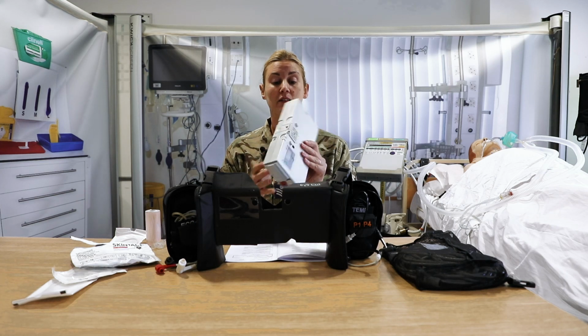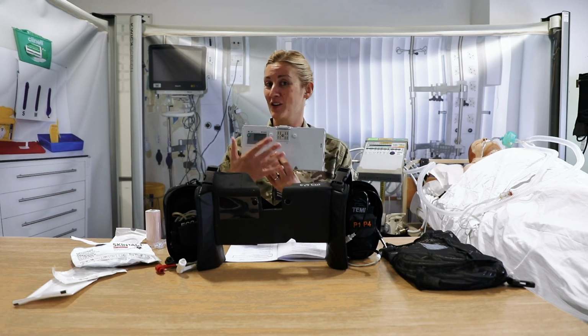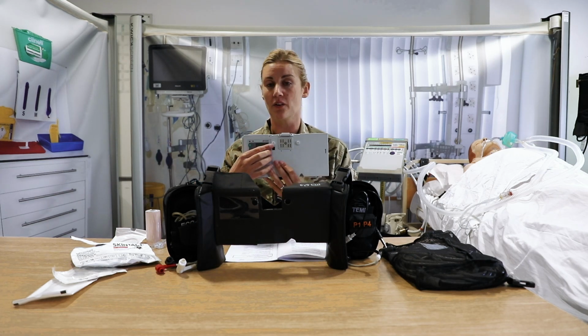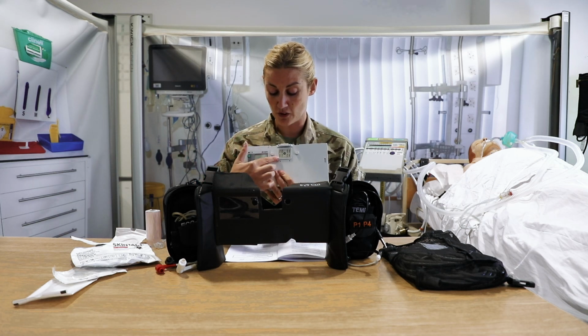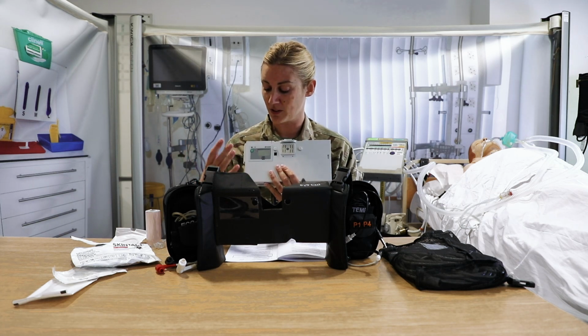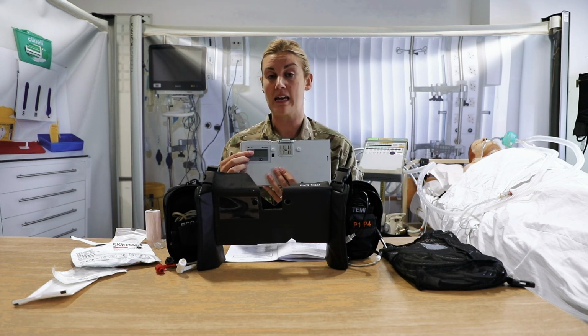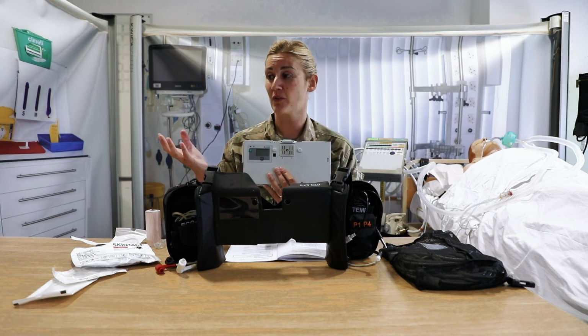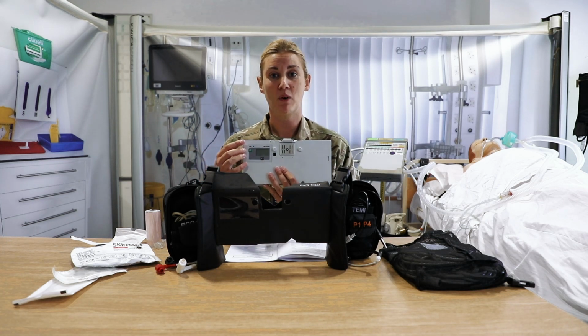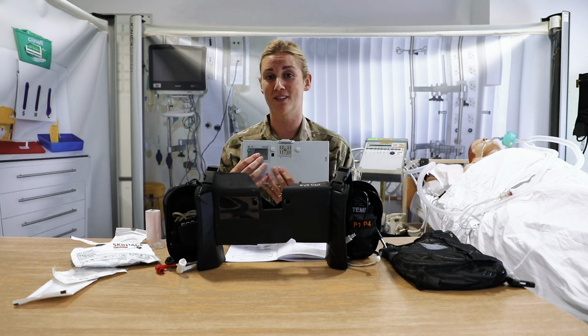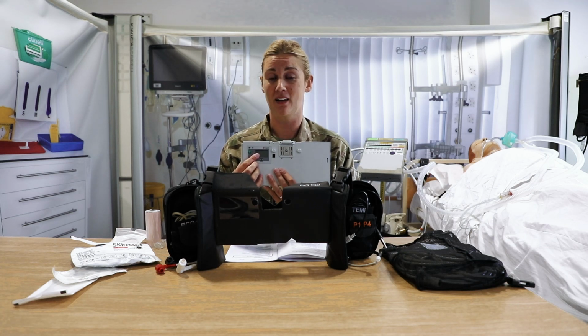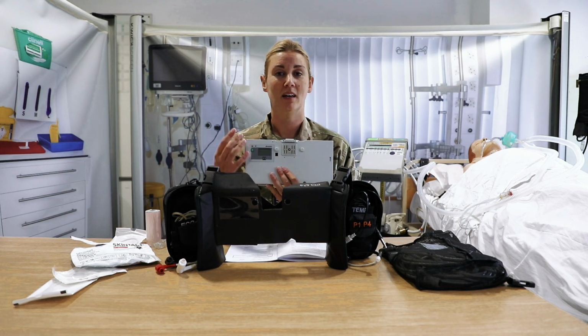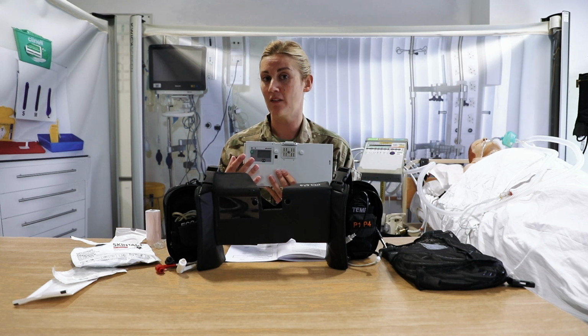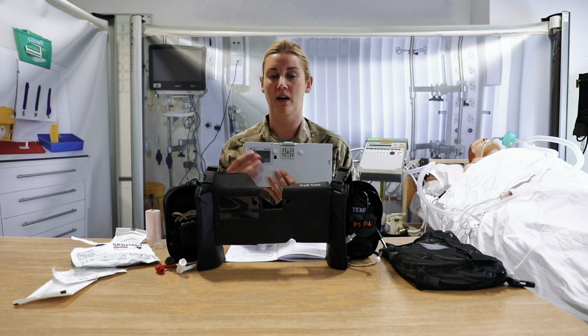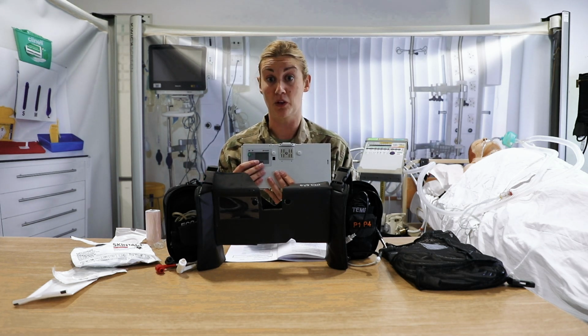So the box itself, you'll notice it looks kind of similar to a lot of the functions we've seen on the other two parts. We've got our connections, we've got our infrared port, but we have a new little window here, which is actually our kind of auxiliary monitor. So if we have a failure with our monitor, then we can see monitored observations on this little liquid crystal display screen. It will give it in text rather than any waveforms, but it's a great little backup for if you have any problems or failure with your monitor.